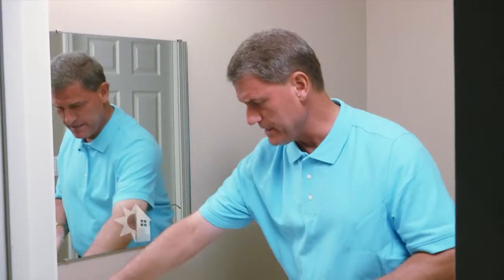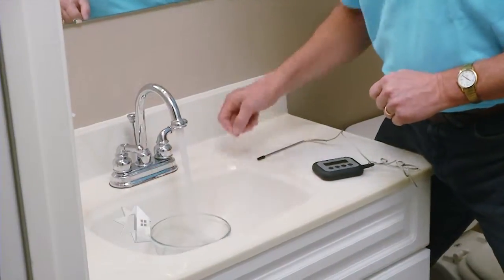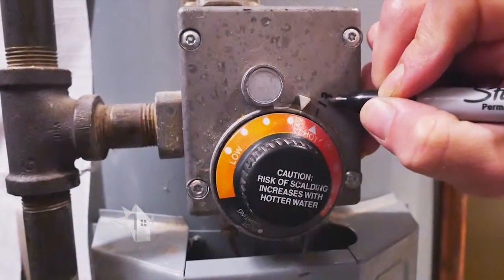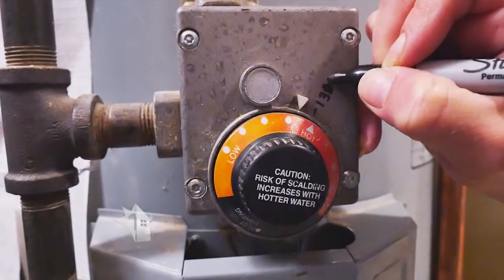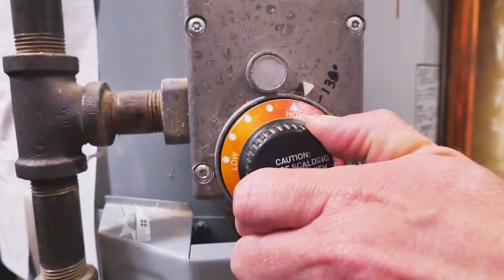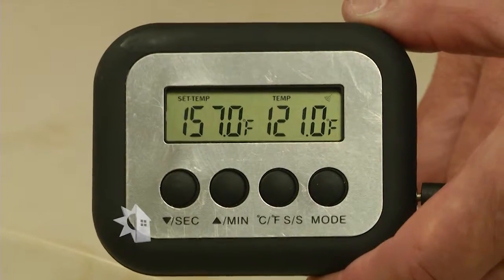Pete is getting a temperature reading at a bathroom furthest from the water heater. Turn on the faucet, let the water heat up, fill a bowl, insert the thermometer, and wait for the reading. The first reading was 138 degrees. Now you can mark the dial on the water heater so you know exactly what the current temperature setting is, then lower the dial a bit, wait a couple of hours, and take the temperature again. The second reading was 121 degrees.